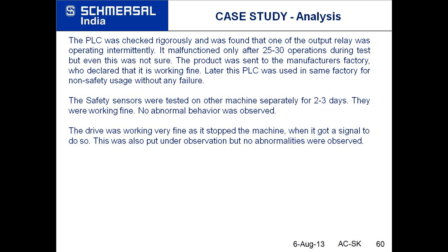The PLC was sent to the manufacturer's factory, which is again a very, very reputed multinational manufacturer of that PLC. And they declared that this product is working very fine. And to tell you the truth, later on, this PLC was used in the same factory, but for a non-safety usage without any failure.